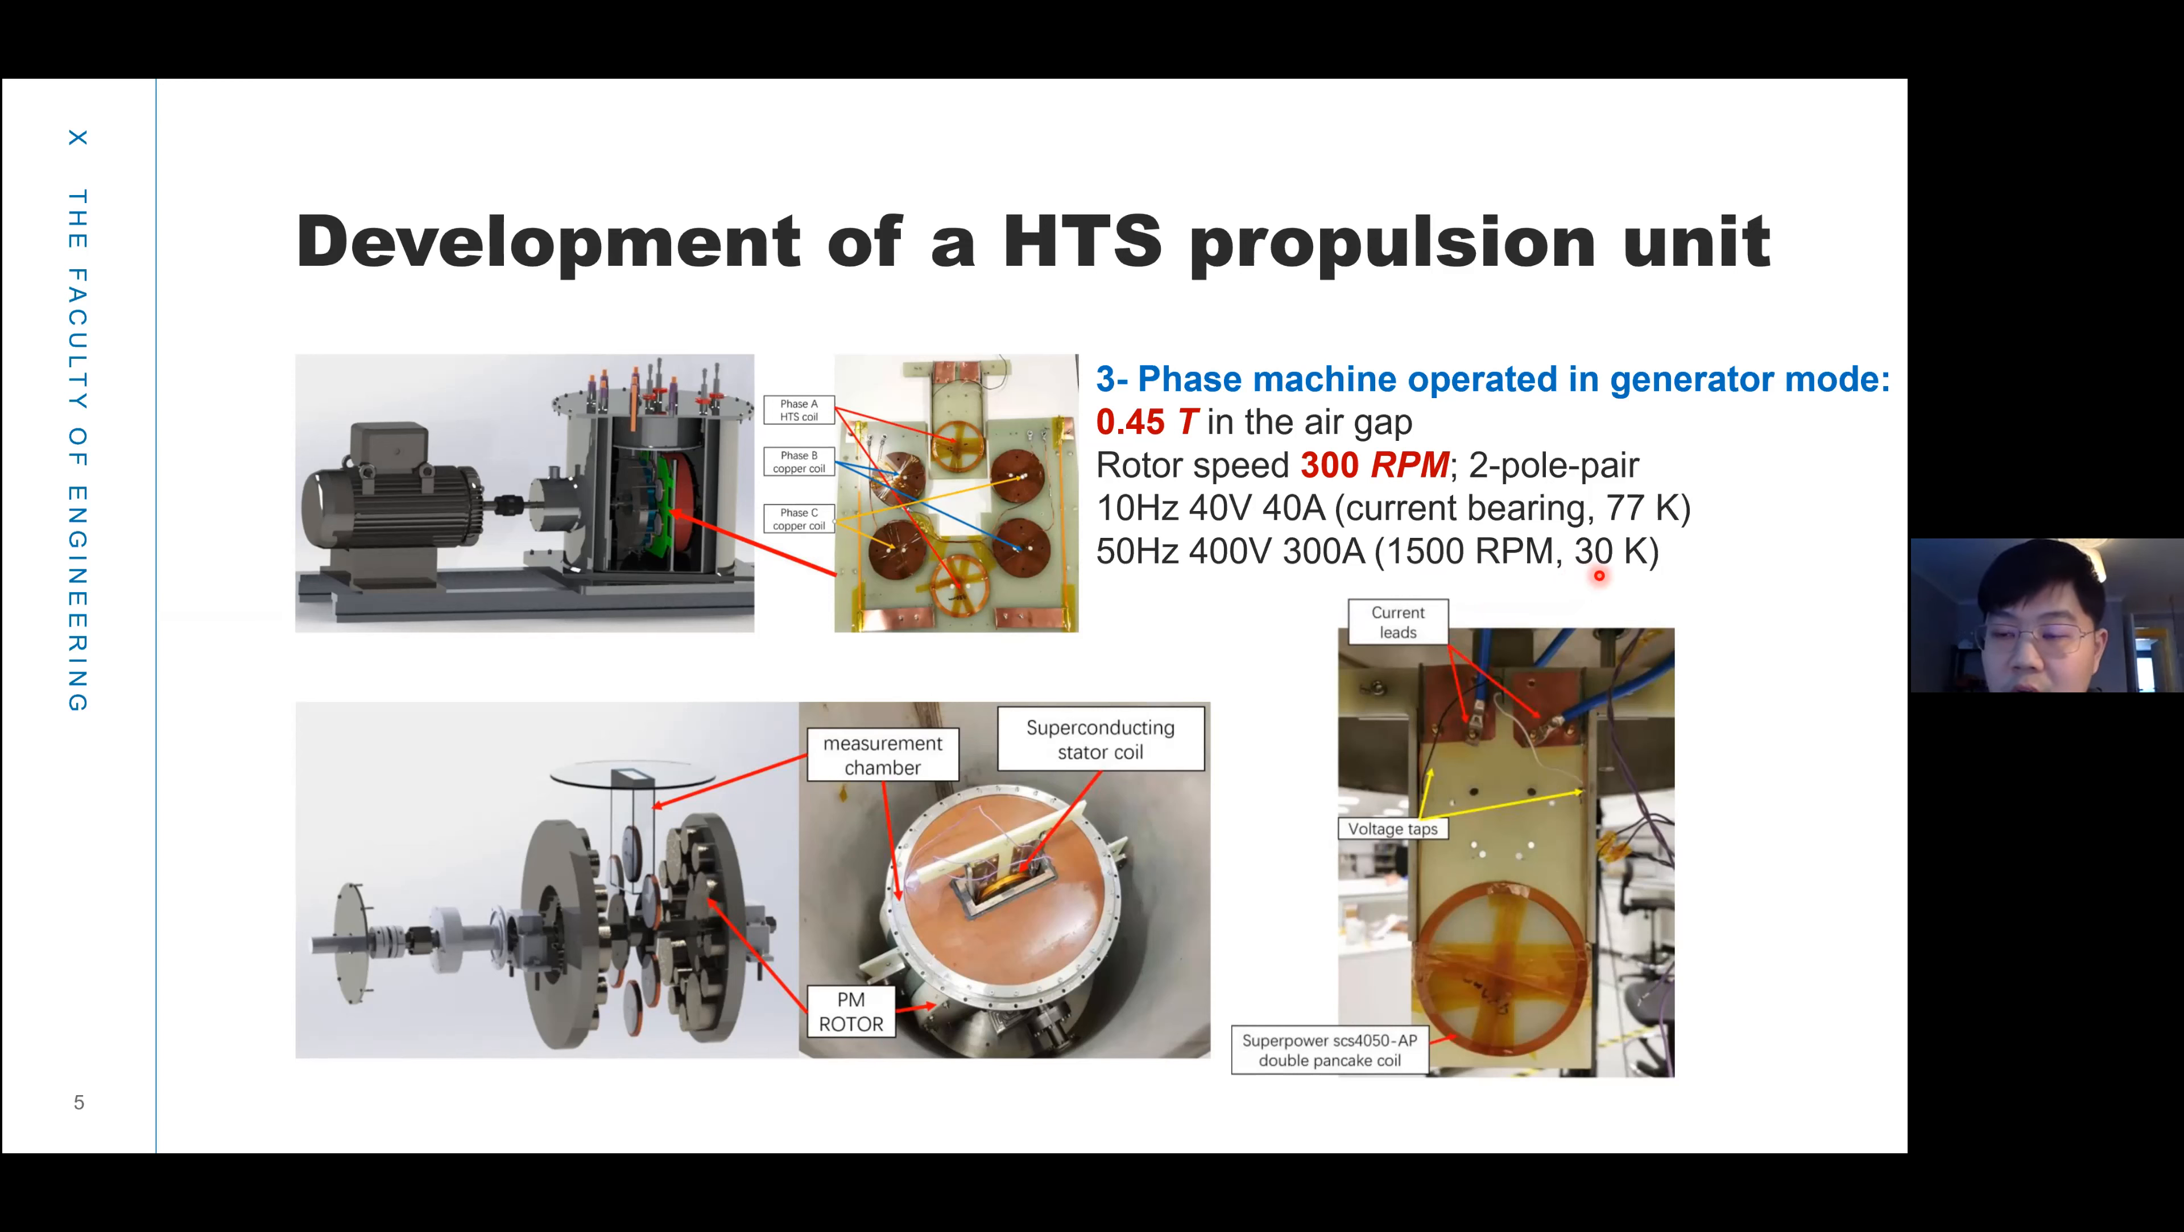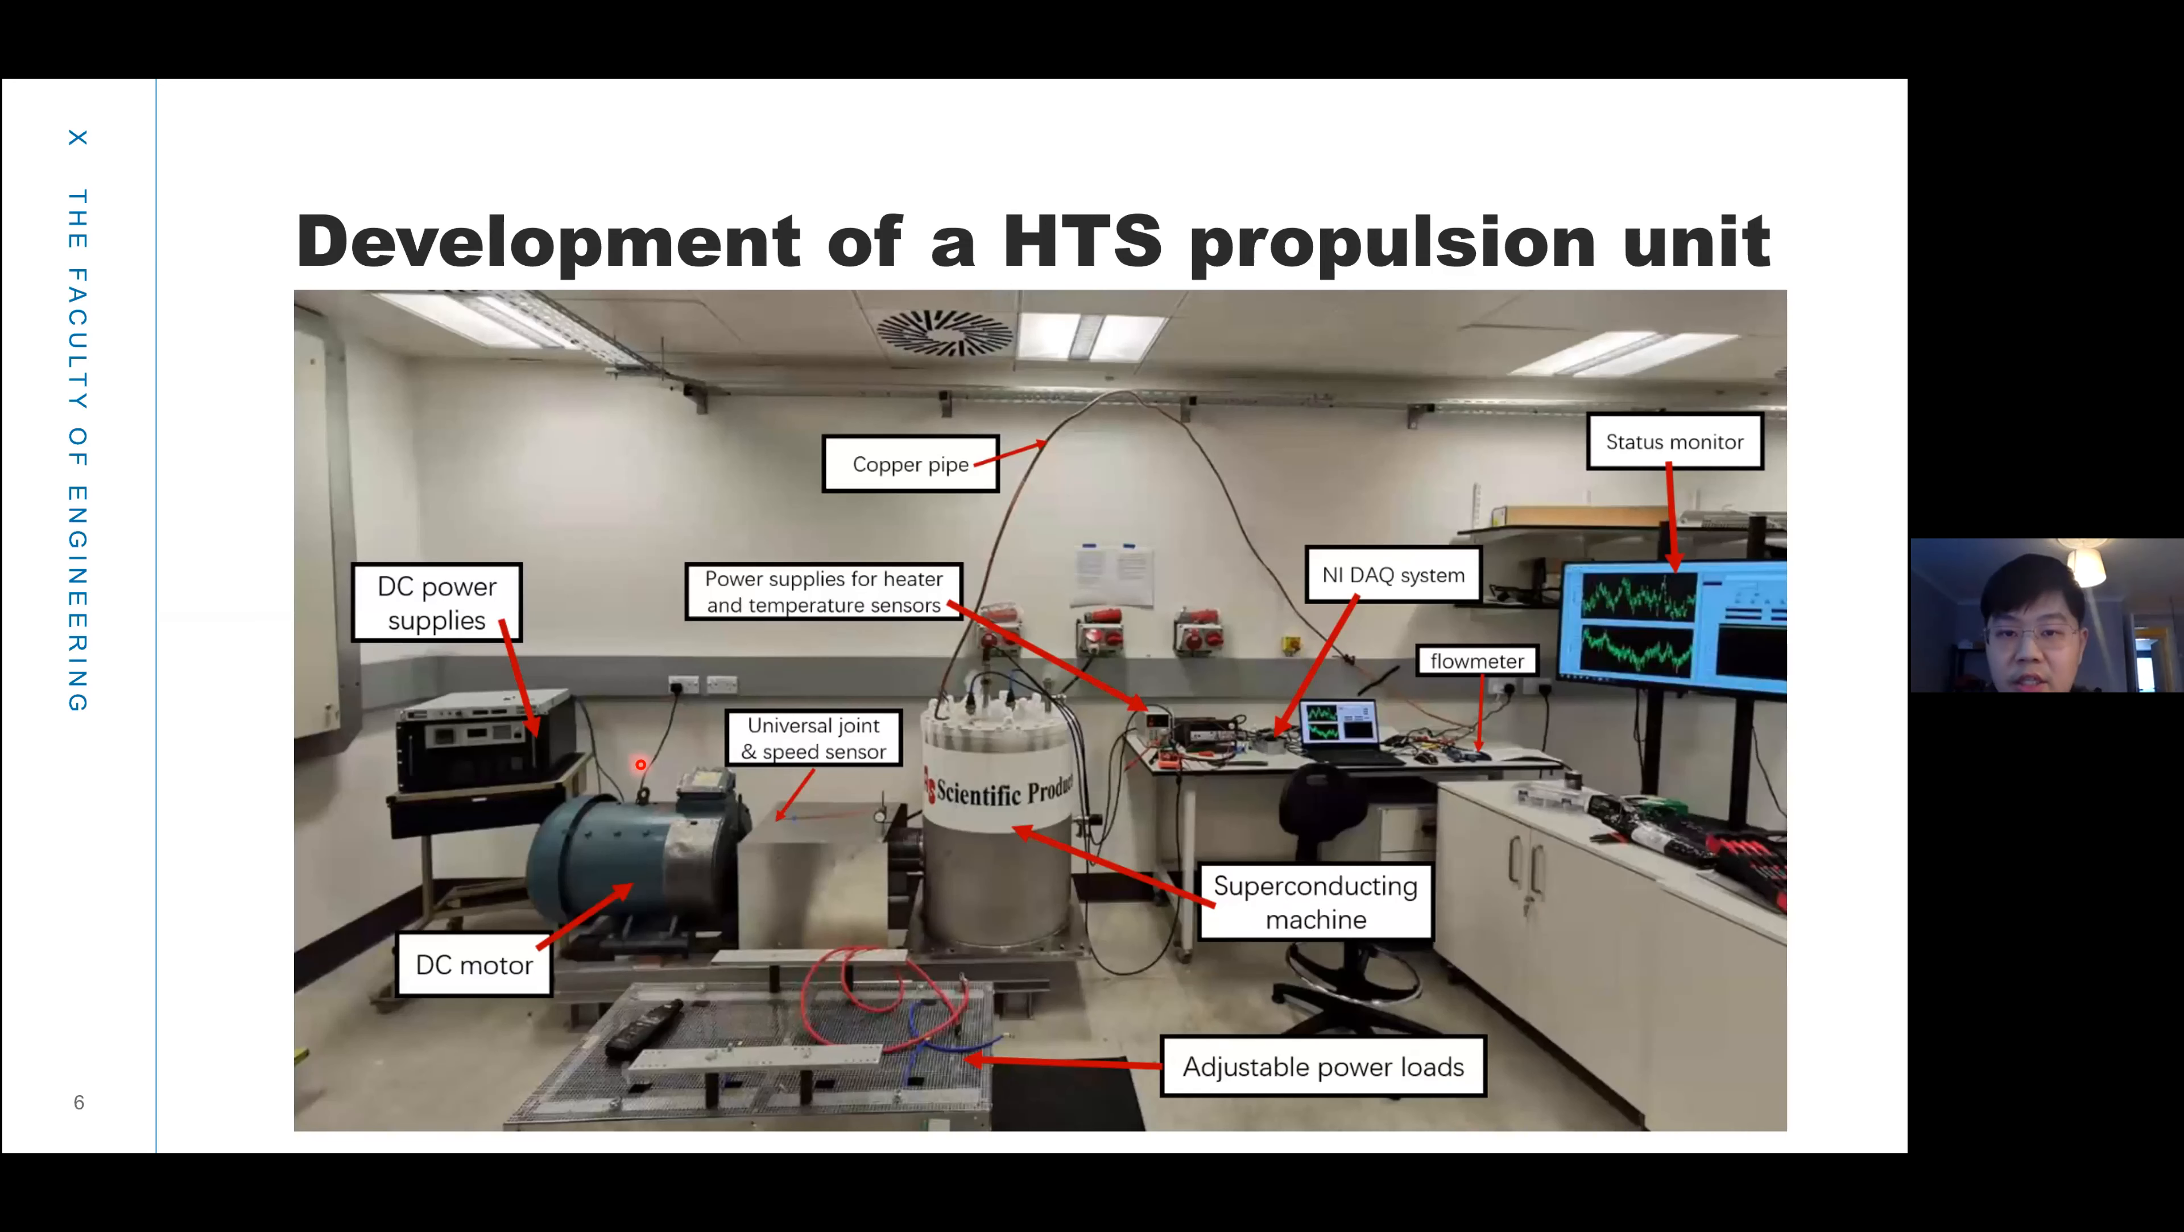The temperature can go down to 30 Kelvin. This is a measurement coil in superconducting phase A, and it was put into a measurement chamber. The measurement chamber has liquid nitrogen inside. Here is a copper pipe connected to a flow meter. If the HTS coil produces heat inside the measurement chamber, then the liquid nitrogen boils off and we can measure the flow rate of the nitrogen gas, and then we can calculate the total heat inside the machine.